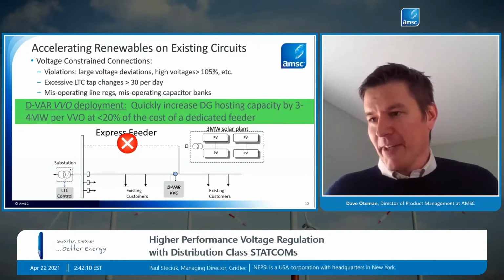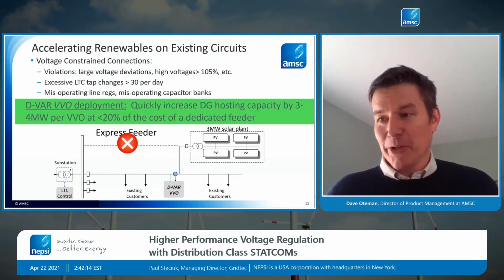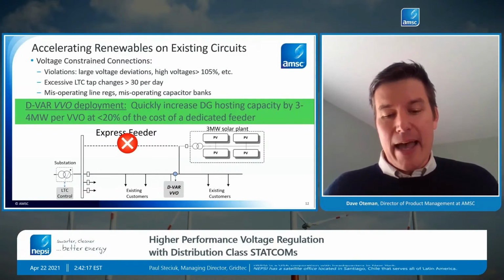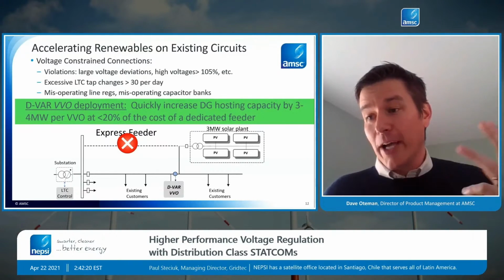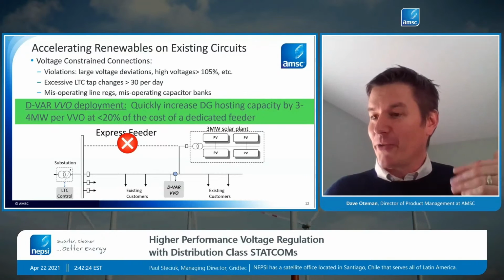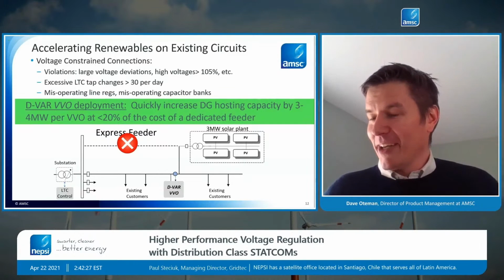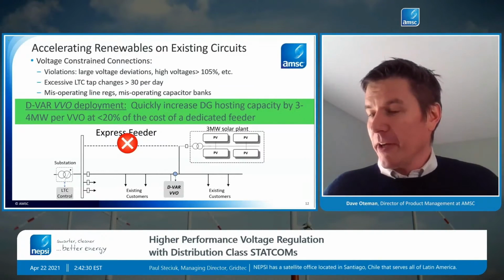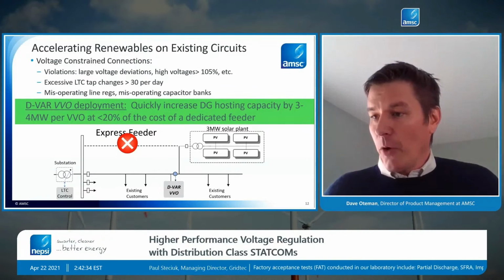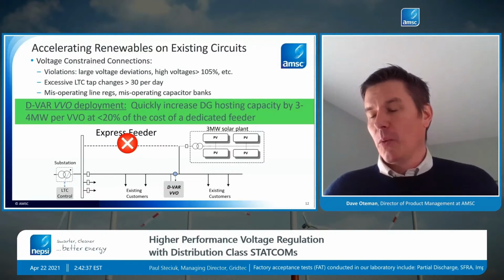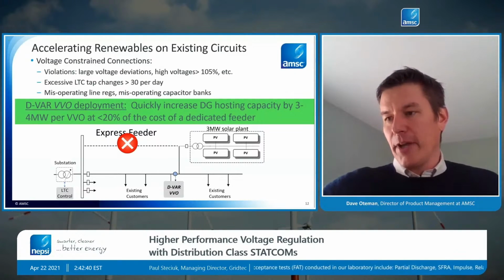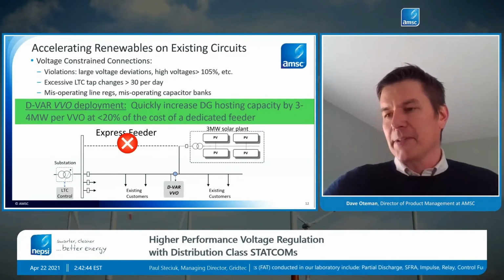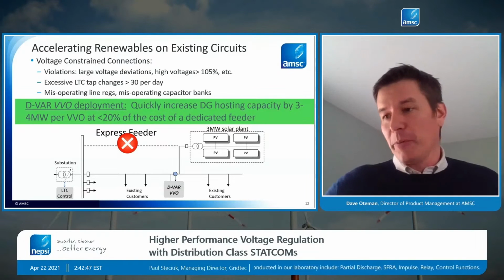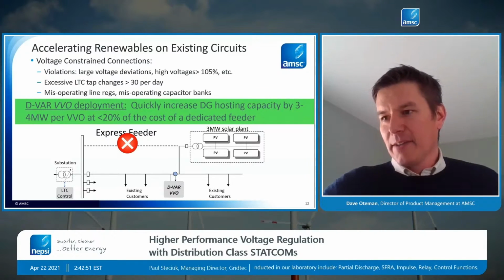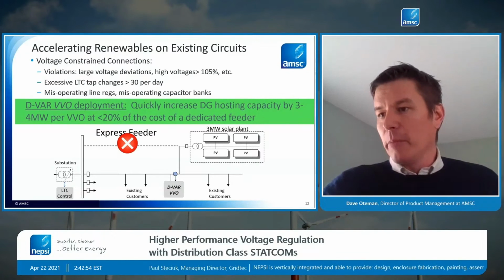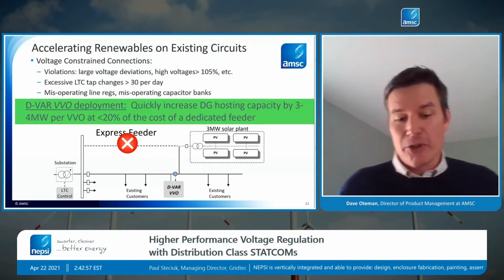One of the differences of connecting variable generation in a distribution system as opposed to transmission is that there are two main differences. Number one, you've got customers in your distribution system, and those high voltage violations and misoperation of mechanical equipment can potentially impact existing customers. So when utilities look at permitting large generators or rooftop solar to come onto the system, they have to be concerned with protecting the power quality of their existing customers. That's number one. Number two, utilities also have to be sure to protect their own assets.